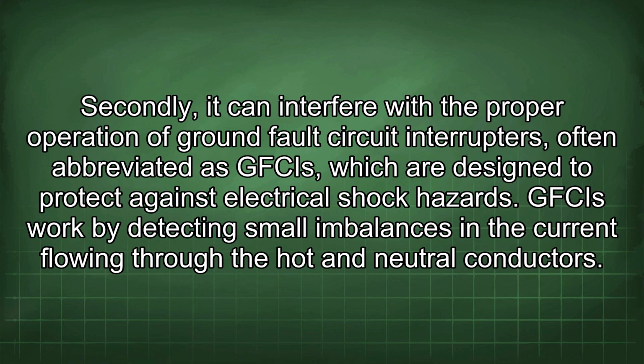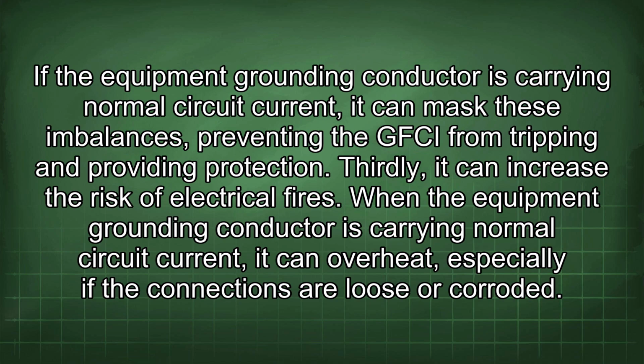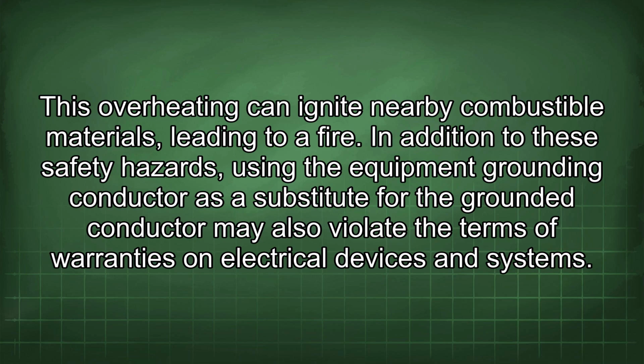GFCIs work by detecting small imbalances in the current flowing through the hot and neutral conductors. If the equipment grounding conductor is carrying normal circuit current, it can mask these imbalances, preventing the GFCI from tripping and providing protection. Thirdly, it can increase the risk of electrical fires. When the equipment grounding conductor is carrying normal circuit current, it can overheat, especially if the connections are loose or corroded. This overheating can ignite nearby combustible materials, leading to a fire.